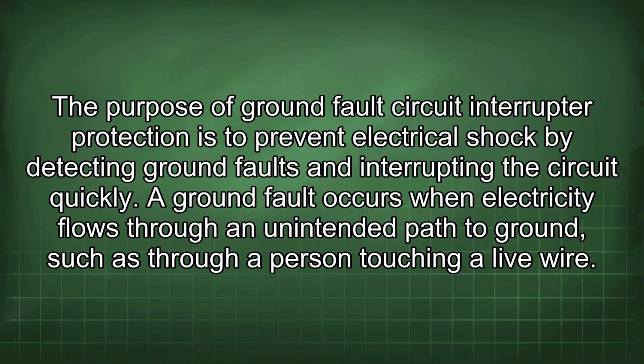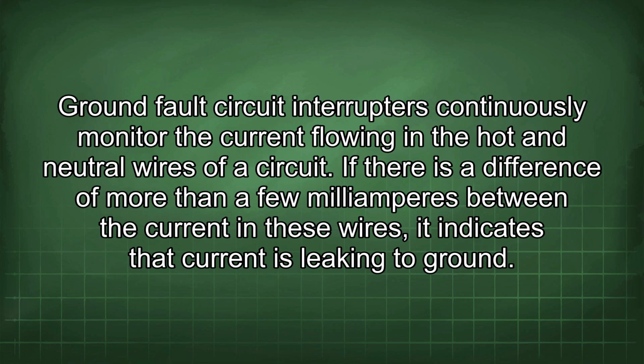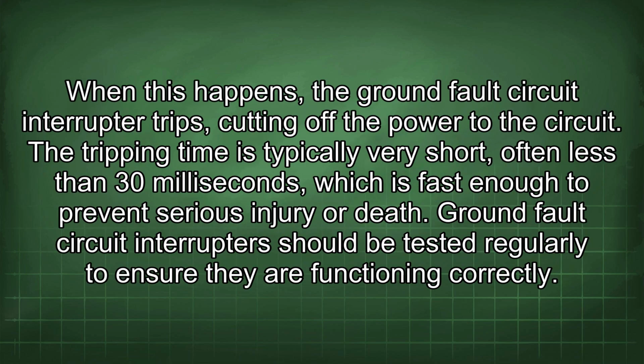The purpose of ground fault circuit interrupter protection is to prevent electrical shock by detecting ground faults and interrupting the circuit quickly. A ground fault occurs when electricity flows through an unintended path to ground, such as through a person touching a live wire. Ground fault circuit interrupters continuously monitor the current flowing in the hot and neutral wires of a circuit. If there is a difference of more than a few milliamperes between the current in these wires, it indicates that current is leaking to ground. When this happens, the ground fault circuit interrupter trips, cutting off the power to the circuit. The tripping time is typically very short, often less than 30 milliseconds, which is fast enough to prevent serious injury or death.